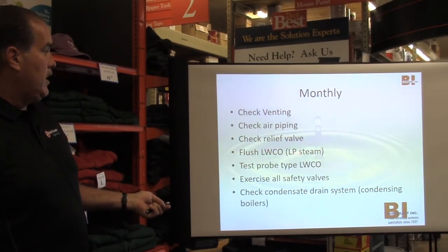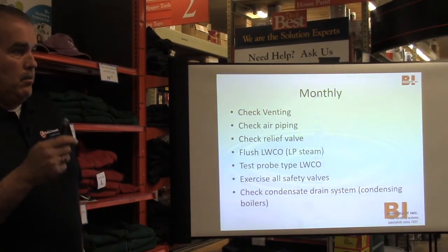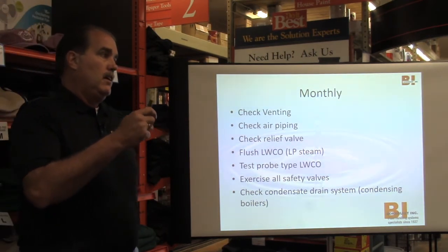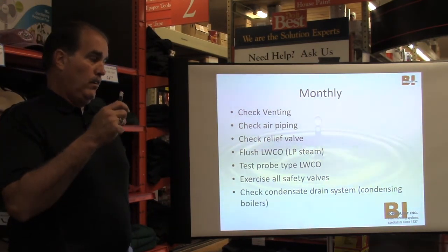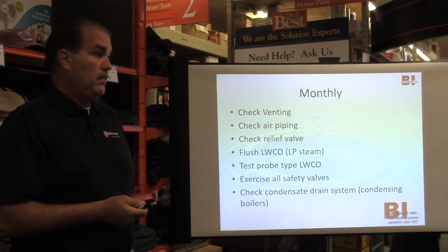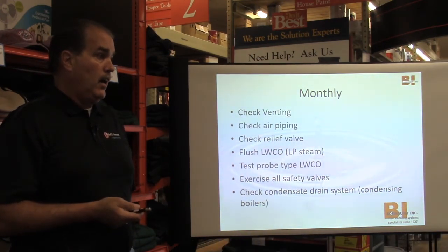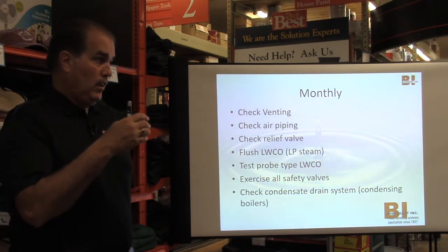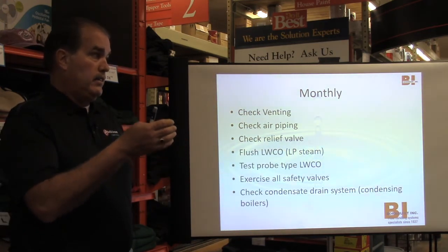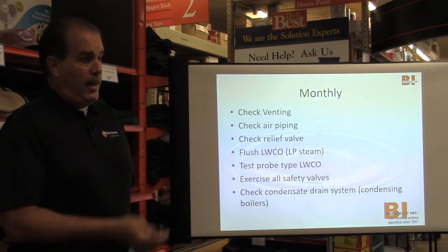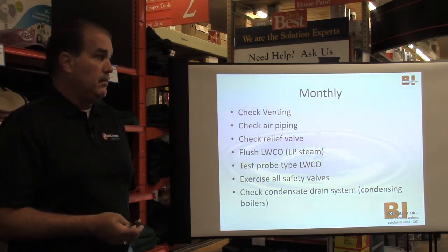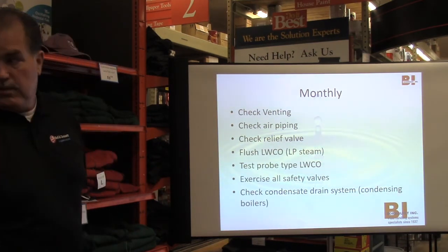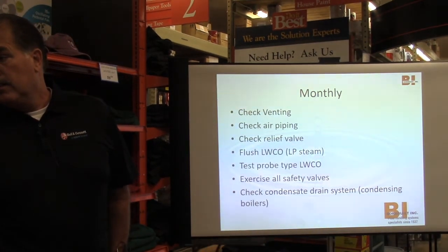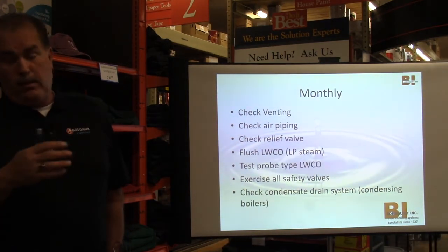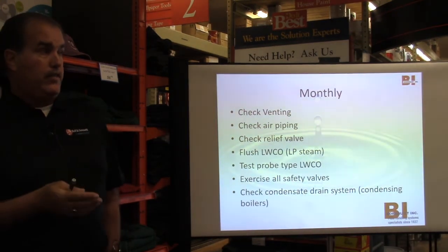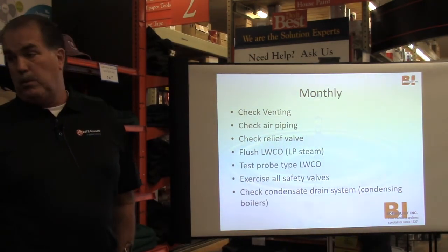One thing you can do is, when you flush your low water cutoff with the system running, if you flush enough water, it should turn your burner off. And now you've tested your low water cutoff too. I tell you, you've got to do it when it's running. It's not going to run for long, because once you flush that out, it should turn the burner off on a steam system, and that's normal. That also checks your low water cutoff. And depending on the time delays, it could turn your feeder on too, which you're going to need anyway because you just pulled water out of the system.